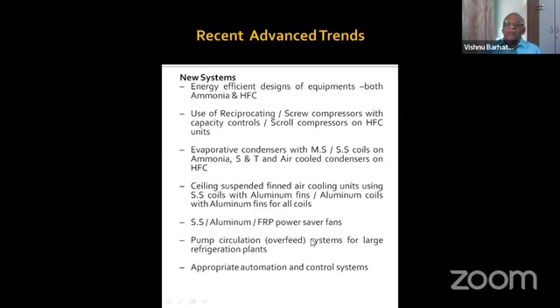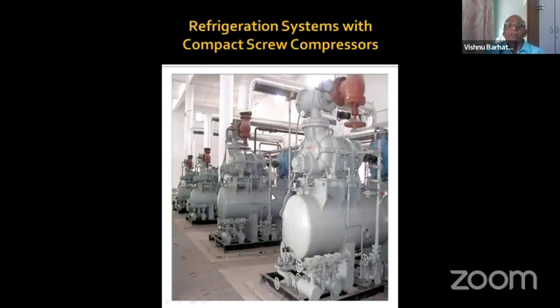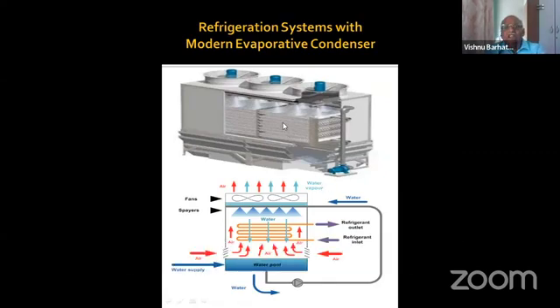Again, in the system, pump circulation systems are very much used, which increases the efficiency. Wetted surface of the heat transfer areas also increases, so thereby a minimum 10 to 15% power saving is also there. Then along with that, a lot of automation and control systems have been developed as per the need of the customer. Now see, this is the photograph of a screw compressor. This is mounted on the vessel, and this is a compact type compressor now being used in large installations. Now this is an evaporative condenser. Earlier, shell and tube or atmospheric condensers were being used, but now this is the most efficient one. It has a diagram here, which will give very high efficiency of the refrigeration system.